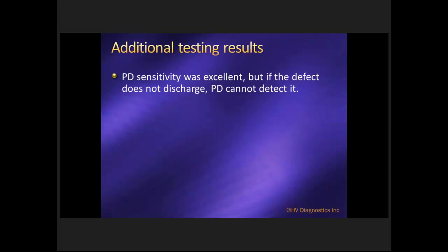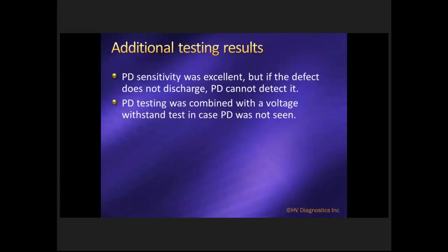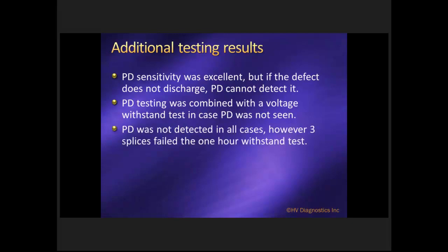The additional test results are quite interesting. The PD sensitivity was great on a very long length of cable. But obviously, if there's a defect in the cable and it doesn't generate PD, as I mentioned earlier, PD won't detect it. If you remember, we were also applying voltage throughout this whole process. We are going offline and elevating the voltage. That's an important part of it, because not only is PD giving you some information, but the withstand test itself, not just pass-fail, tells you if the dielectric integrity of the cable is good. So PD was not detected in all cases. However, importantly, three splices failed the one hour withstand test.